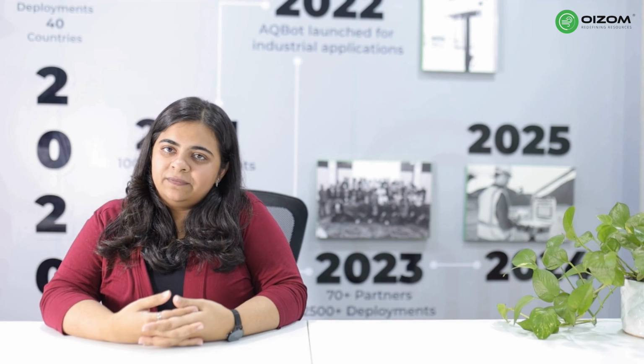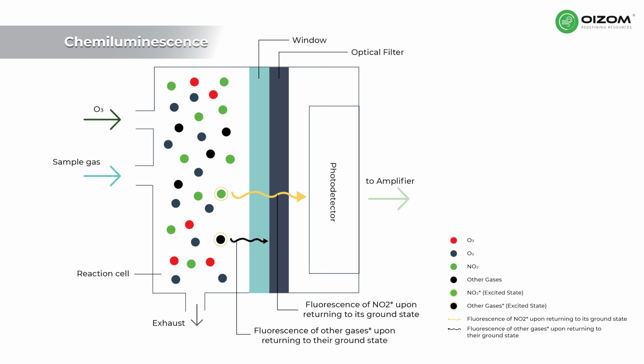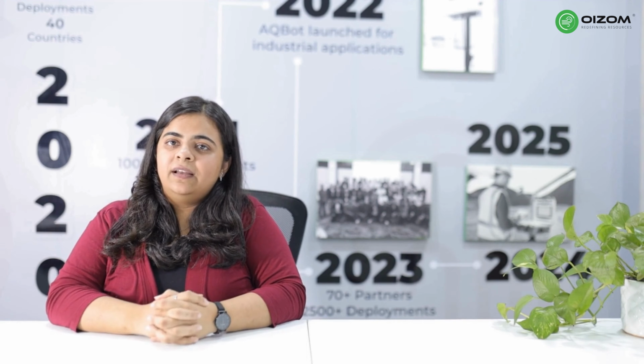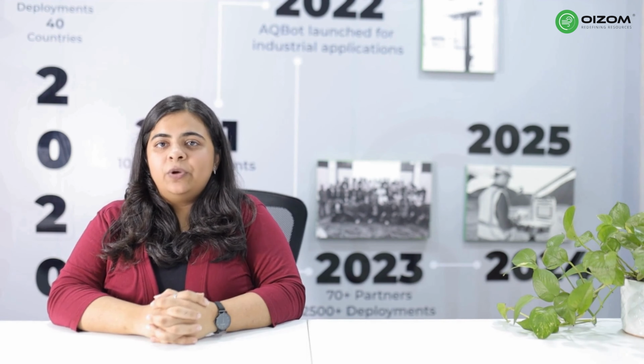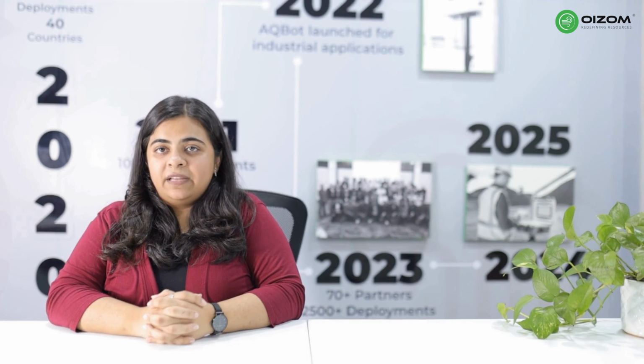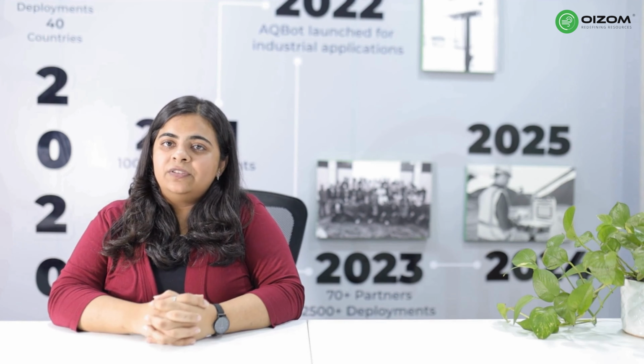Now, let's explore the ways to monitor nitric oxide. 1. Chemiluminescence, the gold standard. This method uses a reaction between NO and ozone, O3, that produces light. The brightness of this light tells us how much NO is present. NO2 is measured by converting it into NO, giving a complete picture of NOx levels.